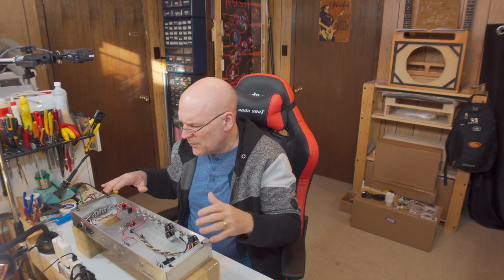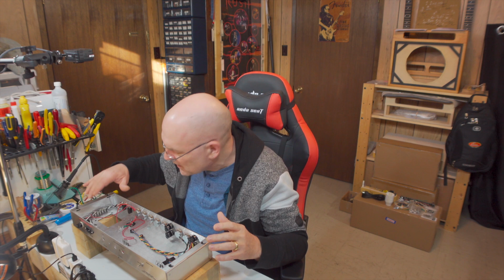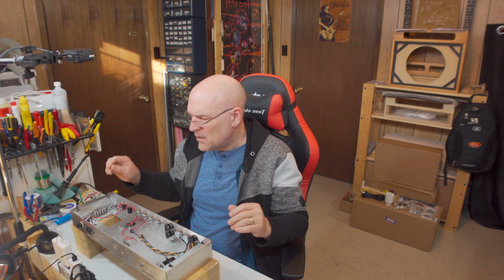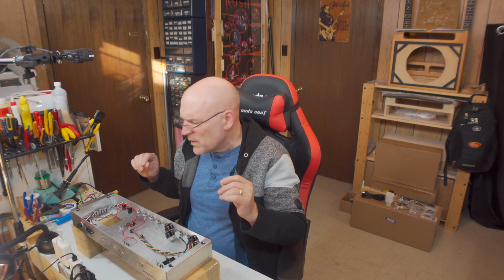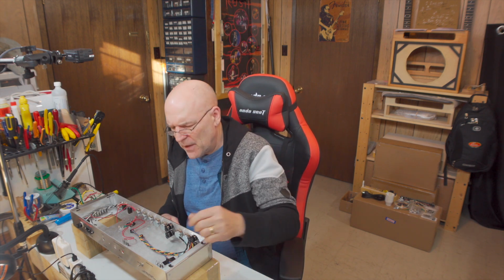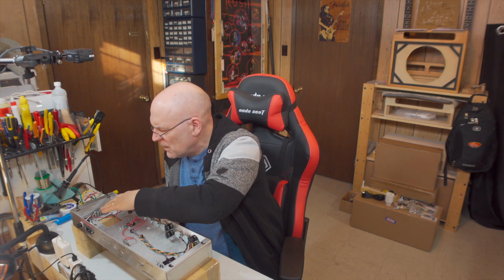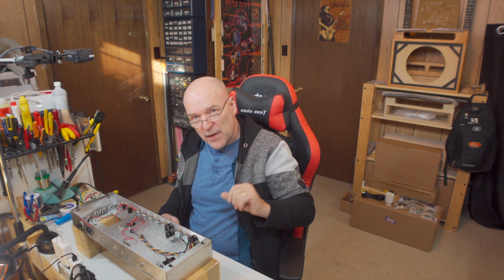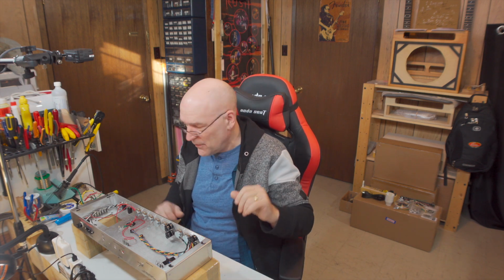Because this was a check of the voltages and just checking that we had the approximate voltages we needed in places, there are no other components installed, no other connections. Basically, that transformer was just connected to these terminals, and then those wires, those connections weren't going anywhere. It was just a good, safe time to check the voltages in the transformer. So once I've removed the transformer, I left everything else wired the way I had it, and then I did troubleshooting. I did tracing. So the first thing I did was I checked the continuity again on the heater string, because one thing I didn't check before was whether there was a short between the black and red wires, and that could have easily caused this problem. In particular, like I say, the damage seems to be right near the output wires for the heater supply.